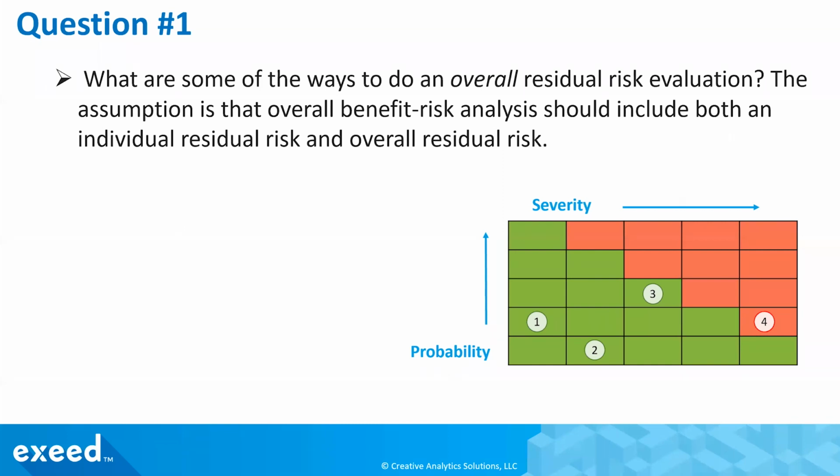There's no prescription or no specified way to go about doing overall. But for individual risks, it's pretty straightforward. You have to do each one of them. Evaluate whether they are acceptable or not. And if they are not, you must do benefit risk. So what Saurabh you are asking is, if it's in green, should I still do benefit risk, right? That's one of the questions you are asking, that people may think you may not need to do it.